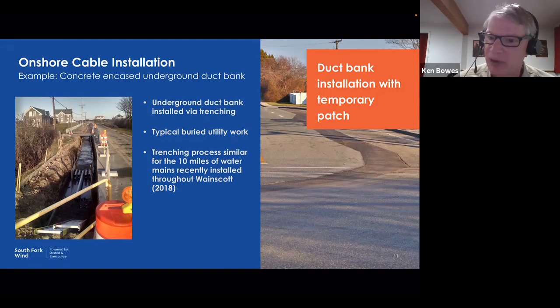But I'm anticipating we'll have to do shoring along the entire route just because of its nature. There are 3 power conductors at this point, so there'll be 3 larger conduits, followed by 2 conduits, 1 each for each fiber optic cable, and then 2 grounding conduits as well. We run a ground conductor adjacent to those power conductors.